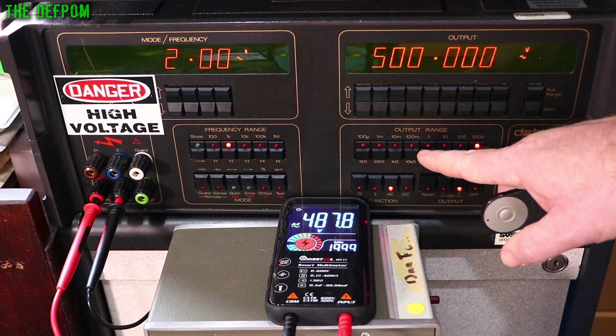Let's do 100 Hz. That looks fine. Okay, let's go down to 10 millivolts. Just check the other end of the scale. Yep, that's fine. Let's do a high voltage, say 500 again. So 500 volts AC at 100 Hz. It's reading 501. Go to 1 kHz, reading 501 as well. Then 2 kHz. Can't read it. Okay, so I did mention that frequency difference there, which is weird. I don't know why it says 6 kHz above 10 volts, because it's obviously not doing that. Basically 1 kHz is the maximum of this thing, really, I'd say. Don't go above 1 kHz on it. It can't read above that.